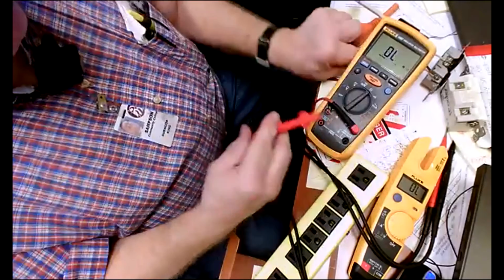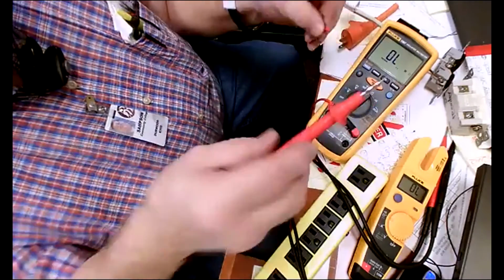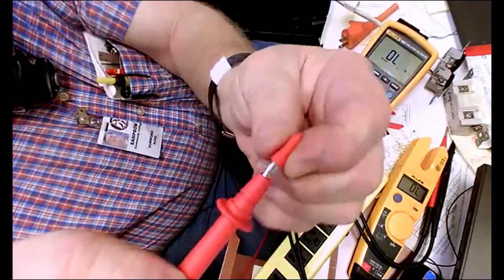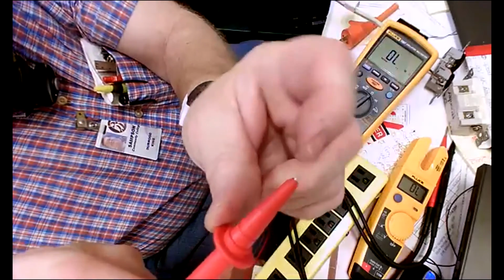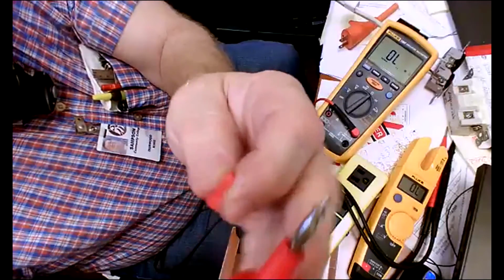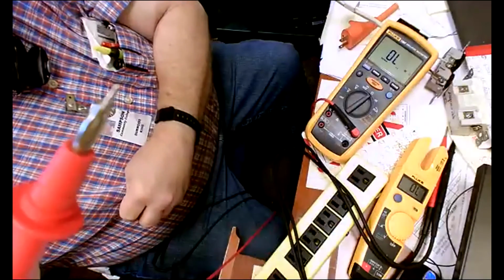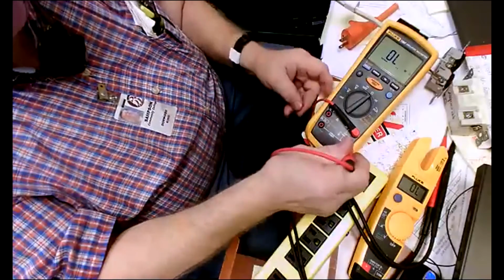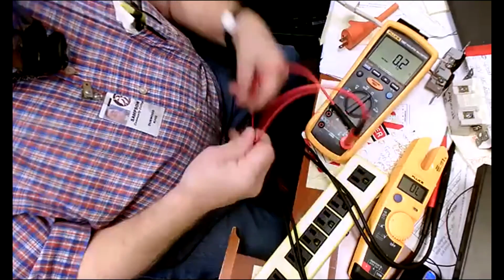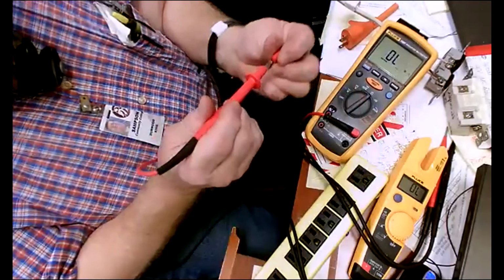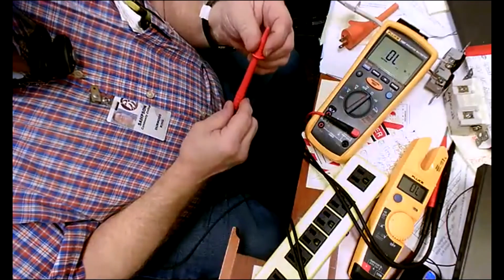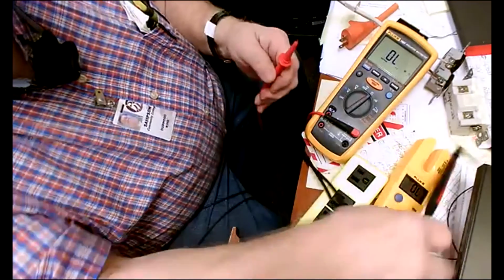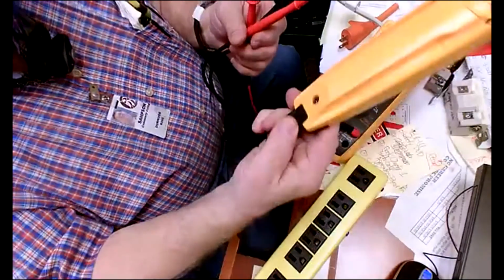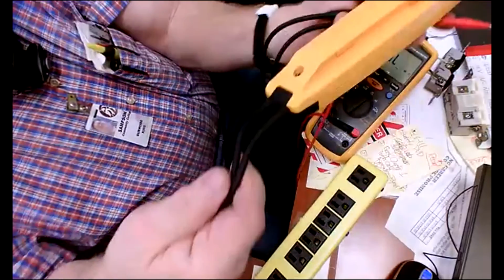You see that? Yep. But you've got to have leads like these, which have shrouds that pull off, where you get safety protection. Then they pull off, and they've actually got a banana plug right there to plug into a regular meter plug. So you can do it that way and just test that one wire. Yeah, his was a basic meter. It was a T5 600, I think. Right. So if the leads are built in, you've got to take the meter apart to get them out, because you can't unplug them.